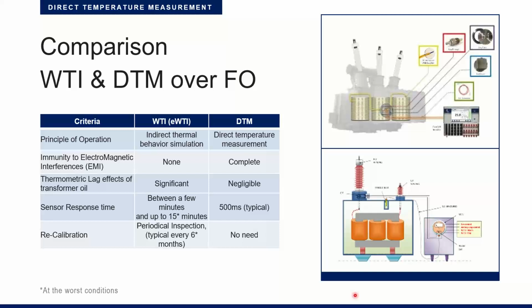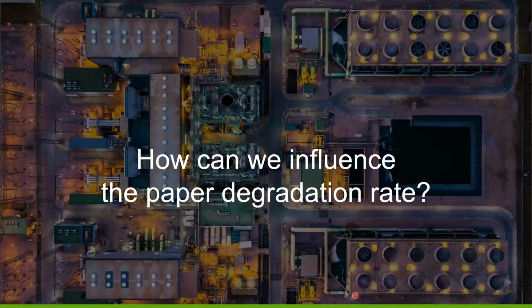You can overload it when you know the temperature. So you can go up to the limits of the maximum allowed hotspot temperatures, control your transformer and overload it. So it's a controlled overload. Yeah. Thank you. Now we know how to measure the temperature more accurately to prevent, let's say, fast aging of the paper.